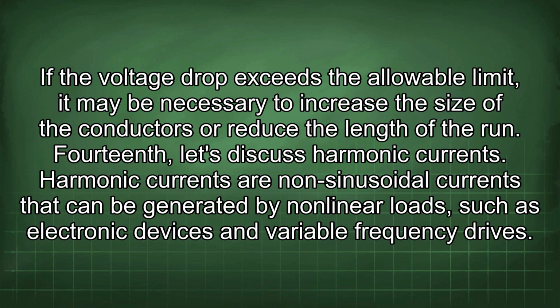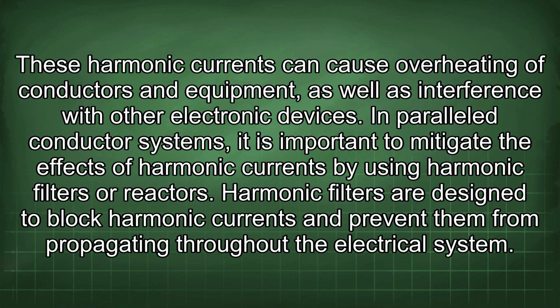14th, let's discuss harmonic currents. Harmonic currents are non-sinusoidal currents that can be generated by nonlinear loads such as electronic devices and variable frequency drives. These harmonic currents can cause overheating of conductors and equipment, as well as interference with other electronic devices. In parallel conductor systems, it is important to mitigate the effects of harmonic currents by using harmonic filters or reactors.